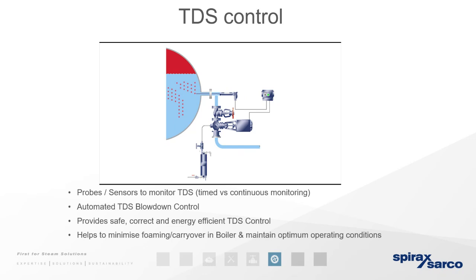So it's an imbalance of pressure. It's the only thing I can think of, an imbalance of pressure. You've got higher pressure at the bottom of the Mobrey than you have at the top. But it shouldn't happen because there's a blowdown procedure on the Mobreys, just like there is on any other level controls. I would suggest to me a blockage of one of those ports. In this particular case, the top entry port.